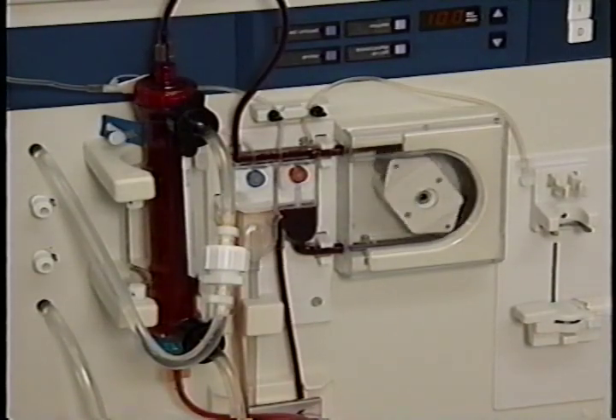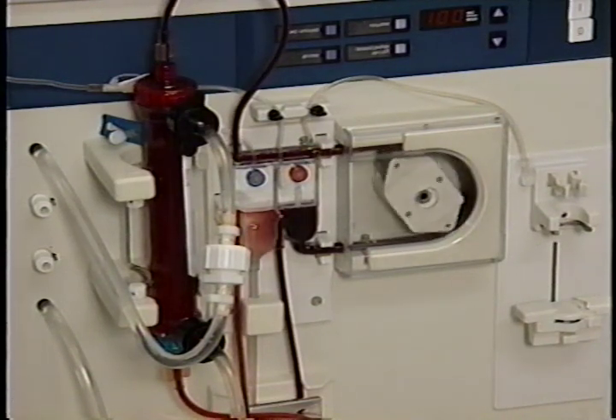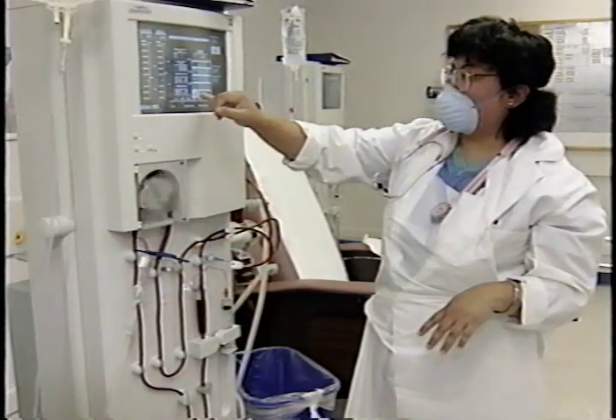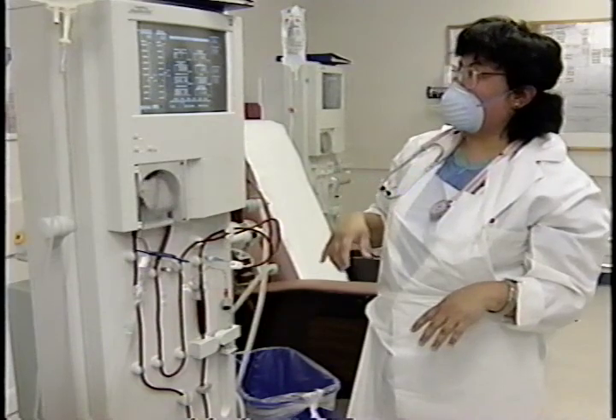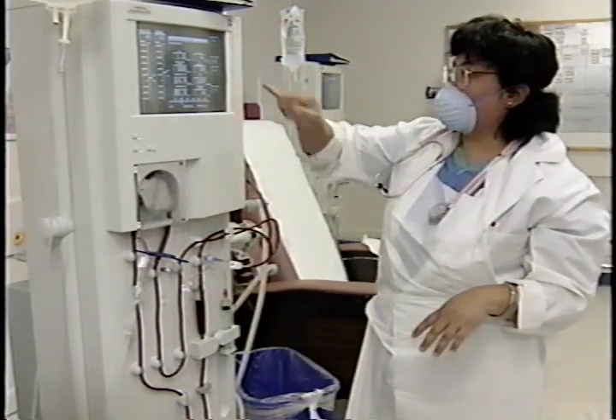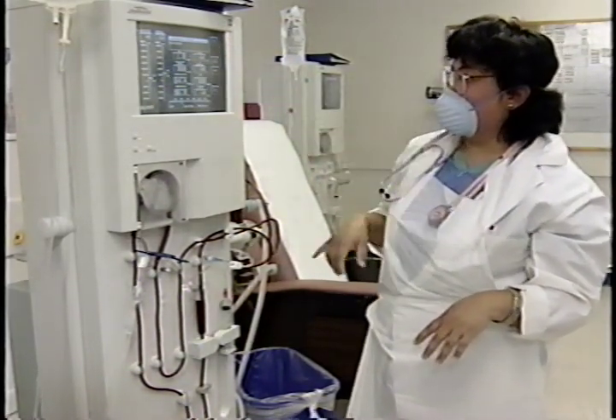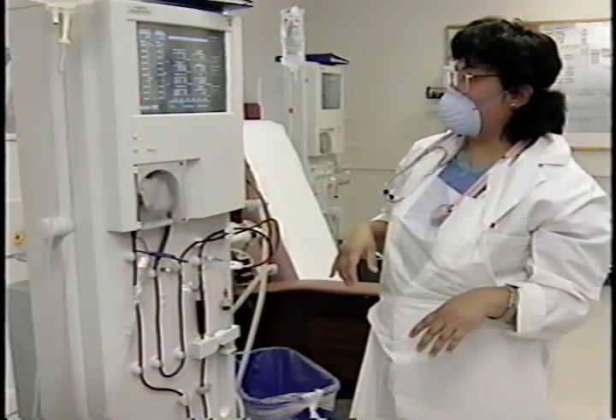If there is a pre-pump arterial drip chamber, observe the flow into the chamber at the initiation of dialysis and again with each monitoring check of the patient and the equipment. This can be used as a good indicator of blood flow. Some facilities monitor the pressure with a pre- or post-pump arterial drip chamber. Other facilities may use a pressure pillow, and still other facilities may not measure the arterial pressure at all.